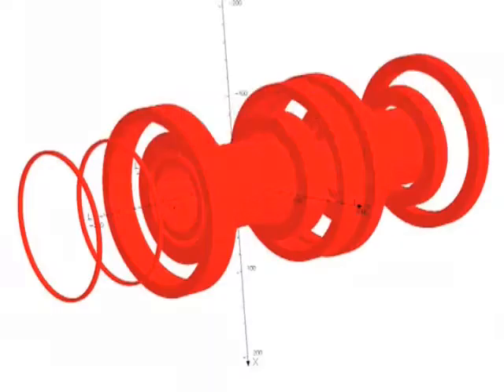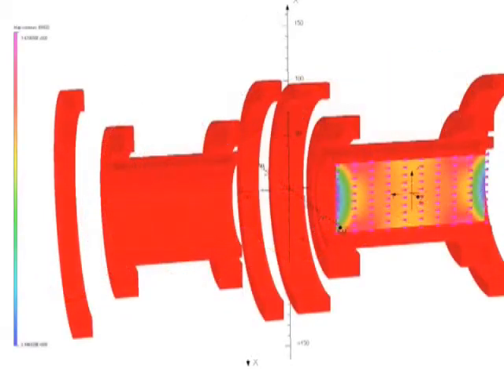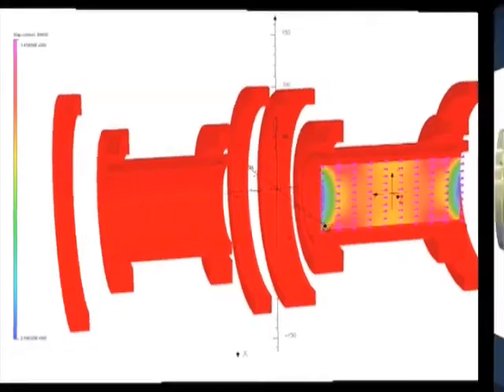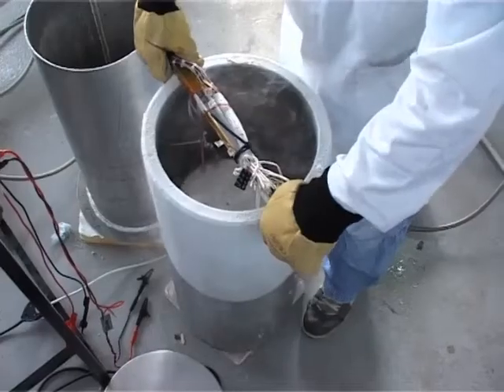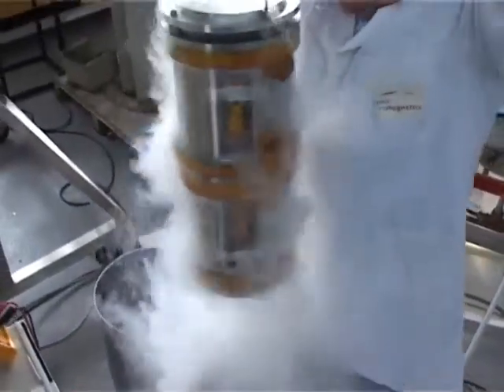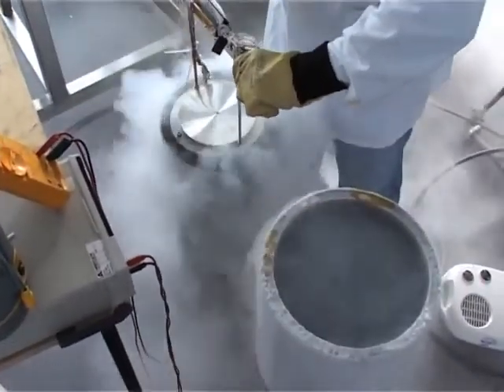I have here a schematic picture of a multiple coil system for a superconducting magnet. This one is actually an adiabatic demagnetisation refrigerator magnet for a space project. It's used to cool an X-ray bolometer to a temperature of around 30 milli-Kelvin. This is how it looks in the hardware — you can see 1, 2, 3, 4 coils on the outside and then there are coils on the inside as well. The majority of this whole mass is just support structure which holds the coils and resists the forces between them, and at the moment it has to be cooled by a cooler to 4 Kelvin.